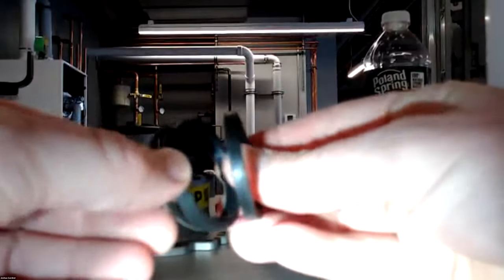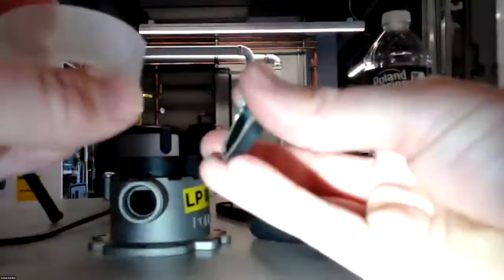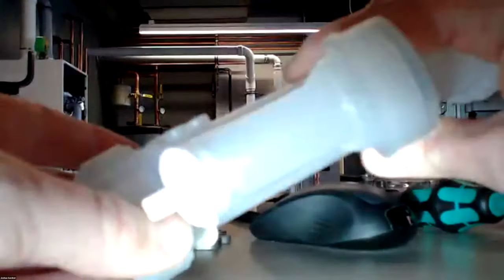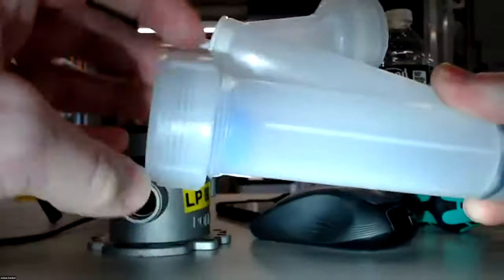I've seen guys on jobs think that these two rubber gaskets, one's a backup. And they take this rubber gasket, they put it off the side, and they put this back together. The metal washer goes on the top. That allows us to spin this without binding up our rubber. All right, it keeps it stationary. But I've seen guys do that, only use the one gasket. This will leak if you use the one gasket. So make sure, keep both those rubber gaskets in there, put it back on, slide this up onto the condensate trap. Condensate nipple coming out of the pan, and then you screw this on and tighten this down.